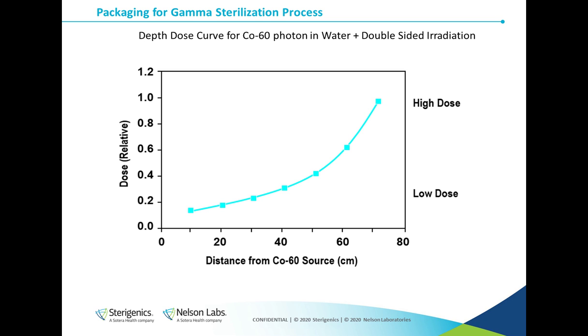So, in gamma sterilization, how do we generate a reasonable process for your product given the depth dose curve discussed on the previous slide? As previously discussed, with respect to dose uniformity ratio, we have to be concerned with the minimum and the maximum dose achieved in the product due to material impacts to both the product and the packaging. We want to keep the dose uniformity ratio as low as possible.